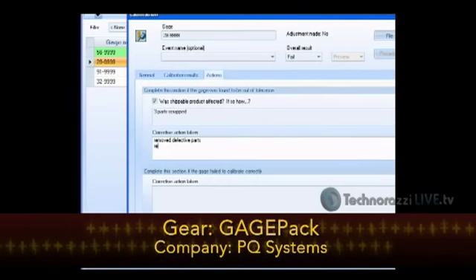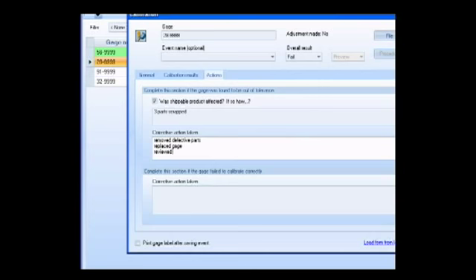We replaced the gauge. And in keeping with true corrective action, we reviewed our training with the inspector involved to make sure they're using the tool right. Now, if we could bring it back into tolerance, we'd be done. But if the gauge would not calibrate correctly, that's the point we would have to replace the gauge.